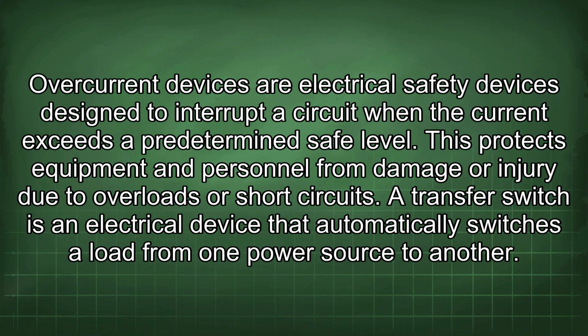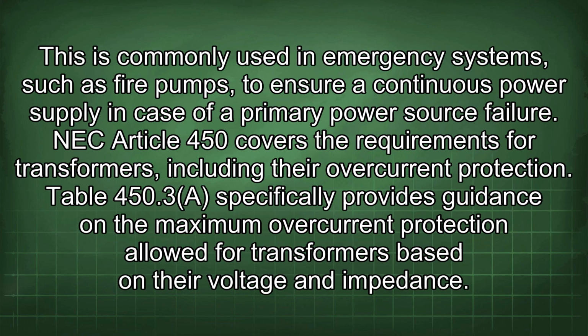A transfer switch is an electrical device that automatically switches a load from one power source to another. This is commonly used in emergency systems such as fire pumps to ensure a continuous power supply in case of a primary power source failure. NEC Article 450 covers the requirements for transformers, including their overcurrent protection. Table 450.3 specifically provides guidance on the maximum overcurrent protection allowed for transformers based on their voltage and impedance.